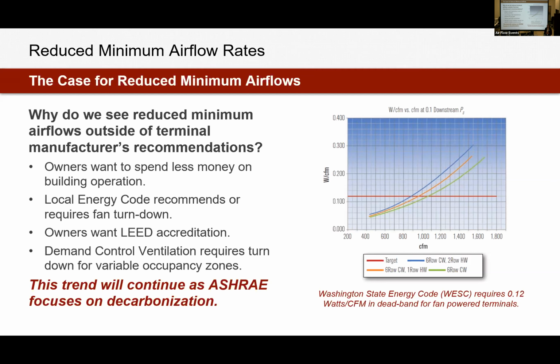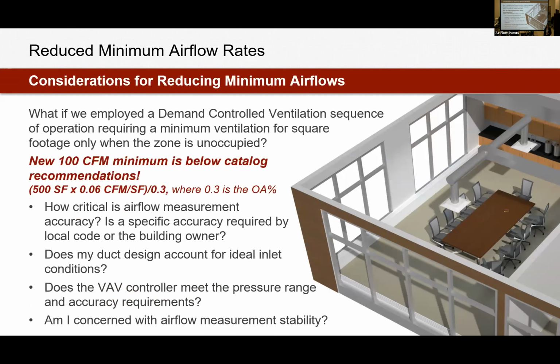And then demand control ventilation. DCV is becoming really popular now, especially in variable occupancy spaces like this auditorium. 90% of the week this auditorium is probably empty, so we don't need to pump it with a lot of fresh air. But when 20 of us are sitting in here, we do want to increase that fresh air. So running demand control ventilation and having those high turn down rates on the ventilation air could be important to save energy in a space like this. So we're seeing this trend continue, and turn down, lower ventilation rates are going to continue to be part of the conversation.